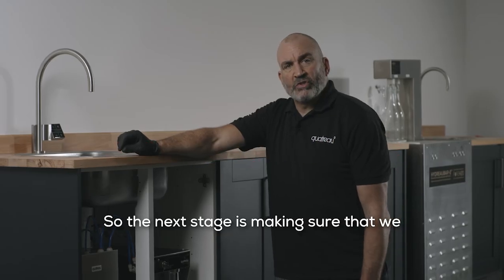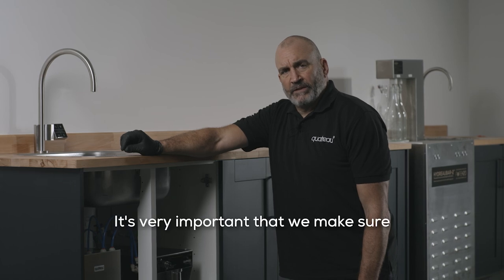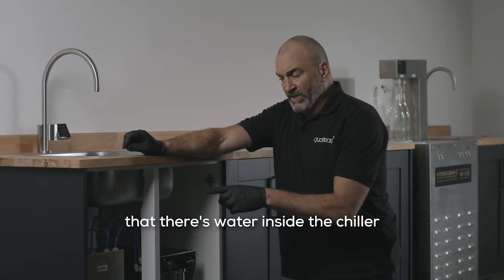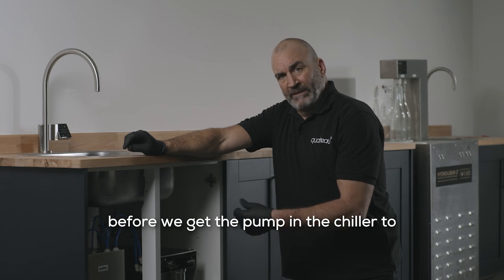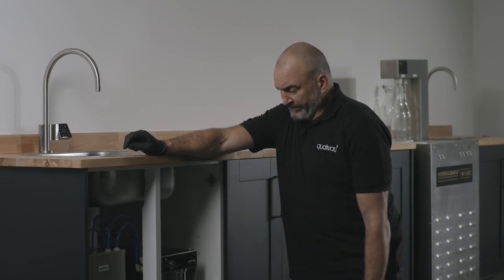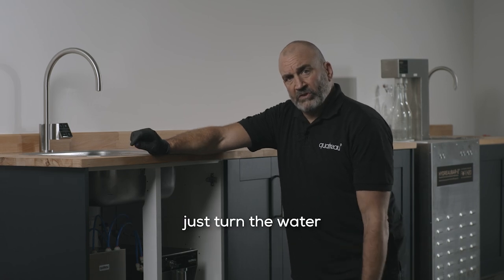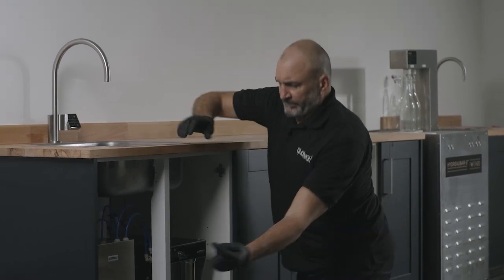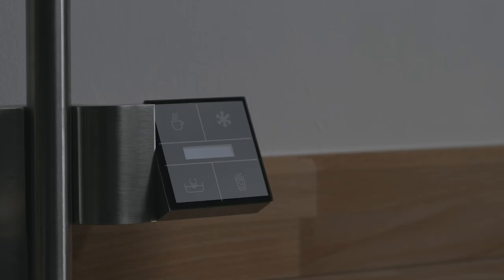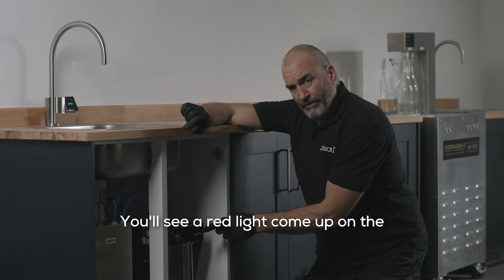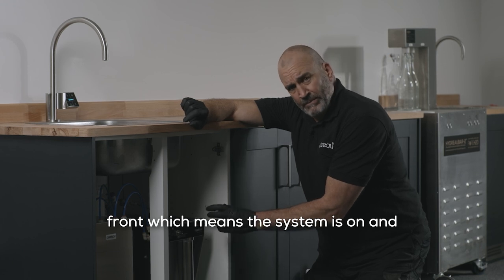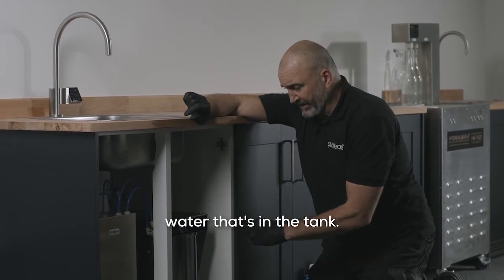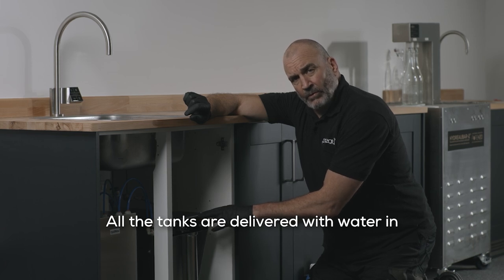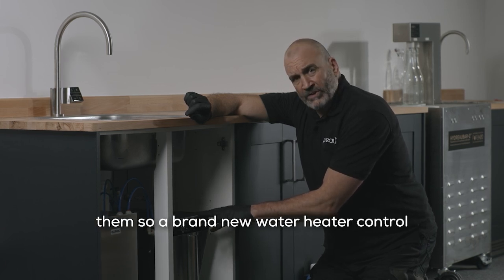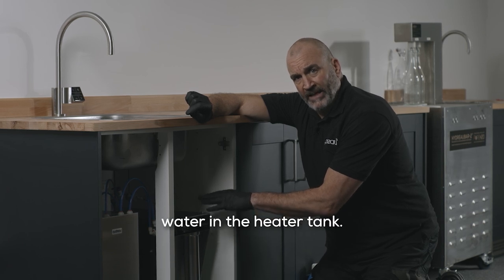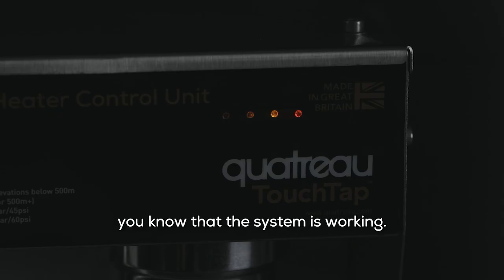So the next stage is making sure that we commission the chiller properly. It's very important that we make sure that there's water inside the chiller before we get the pump in the chiller to work, so it doesn't get damaged. So what we need to do at this point is just turn the water heater control unit on. You'll see a red light come up on the front, which means the system is on and it's actually heating the water that's in the tank. All the tanks are delivered with water in them. So a brand new water heater control unit will always have water in the heater tank. So when you've got a red light on there, you know that the system is working.